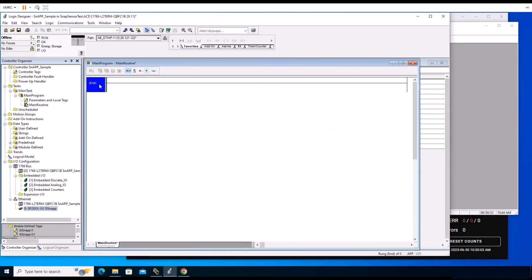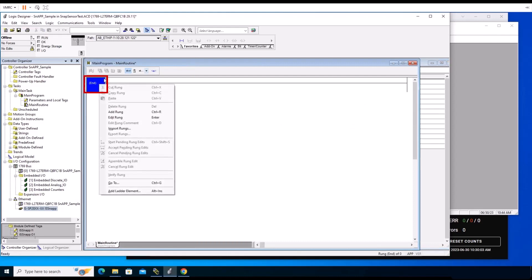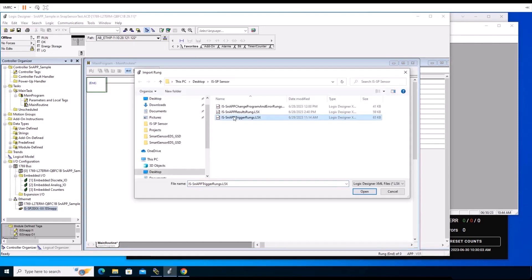We can begin the process of importing the required rungs. Rungs are ladder logic which make up a main routine that is part of the main task scan. It updates with input and output data. It can read inputs from external devices and set outputs to those external devices over Ethernet IP. Locate and right-click the end option displayed in the Main Program Main Routine panel. Click on the Import Rungs option in the list. A new window will appear for Import Configuration.